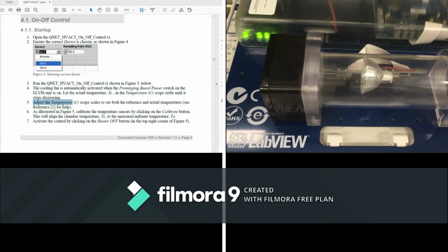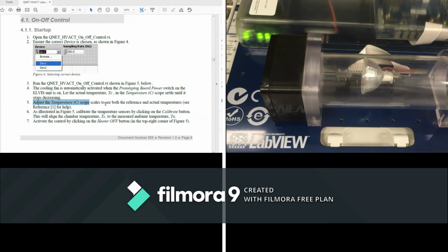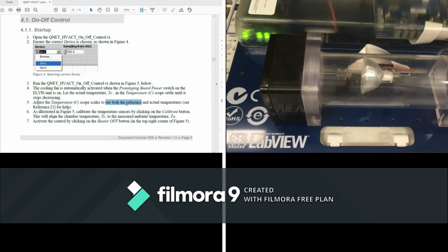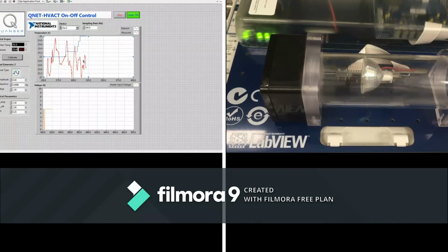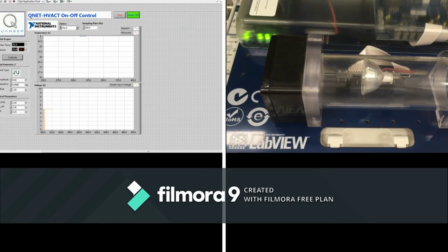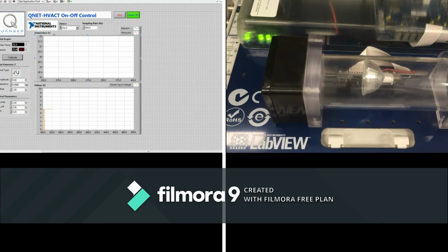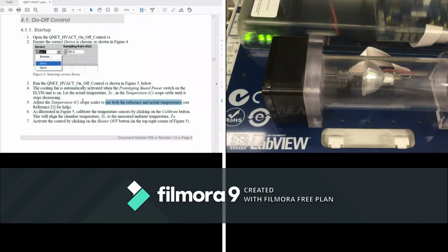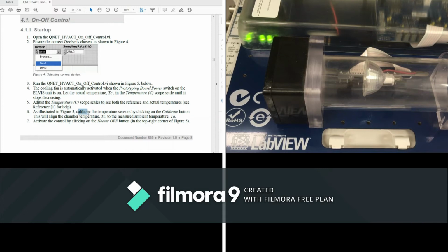So we need to adjust the temperature scope scales to see both reference and actual temperature, because sometimes you will open the software and find that it is starting maybe from 28 and this is 32. Some people will say that we don't have any readings and we have some mistake. Actually the readings are below 28, you only need to check the scales on the scope. Good. So we sometimes need to calibrate the temperature.